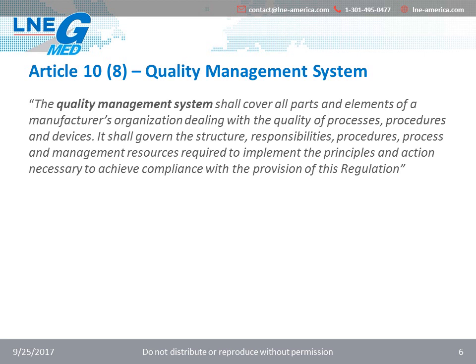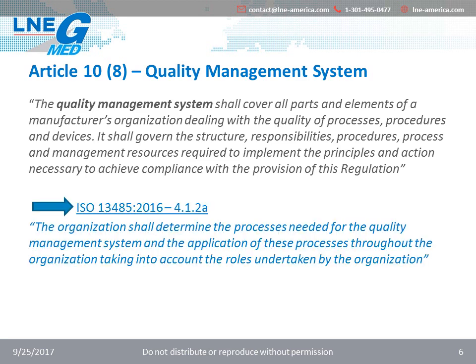The second paragraph of that Section 8 specifies that the quality management system shall cover all parts and elements of the manufacturer organization dealing with the quality of processes, procedures, and devices. In other words, the regulation requires the manufacturer to take into account all aspects of its organization and the life cycle of the device in the development of its QMS. This notion is also found in the ISO 13485:2016 version, in which the standard called for the organization to take into account its role when establishing the quality management system processes, and this is presented in section 4.1.2a.